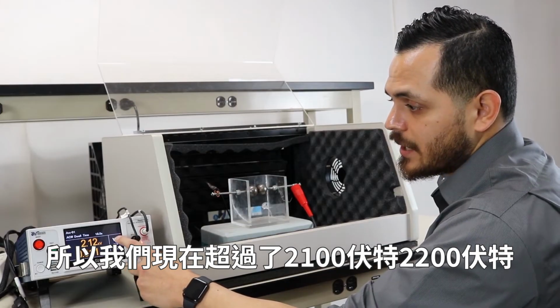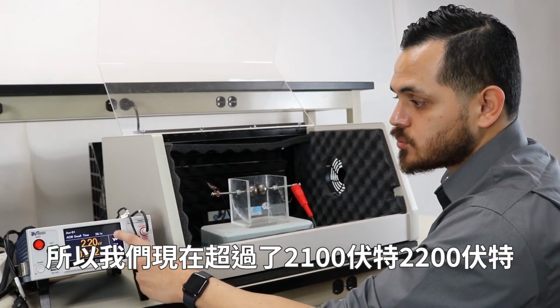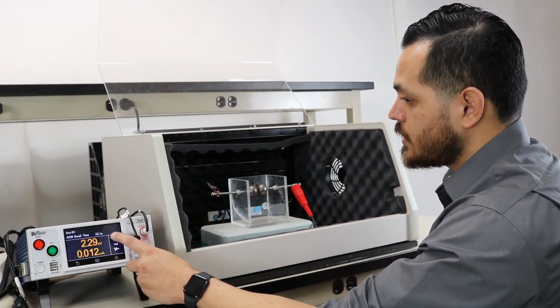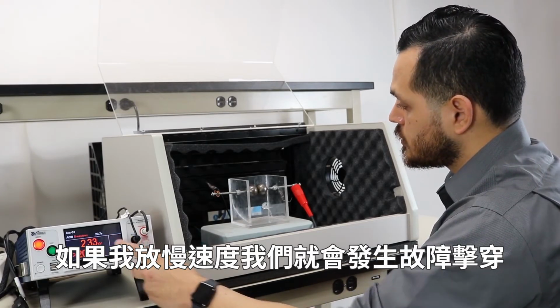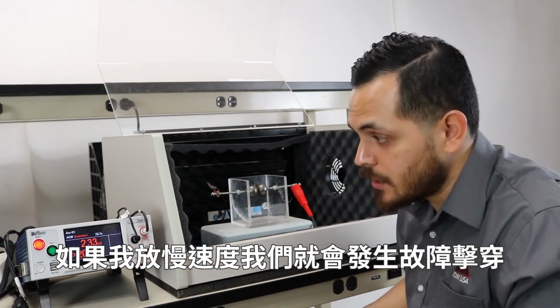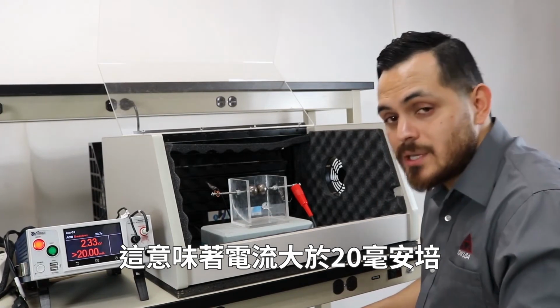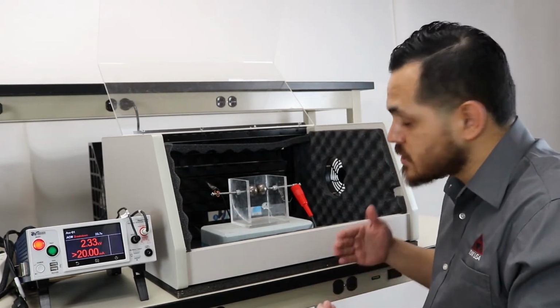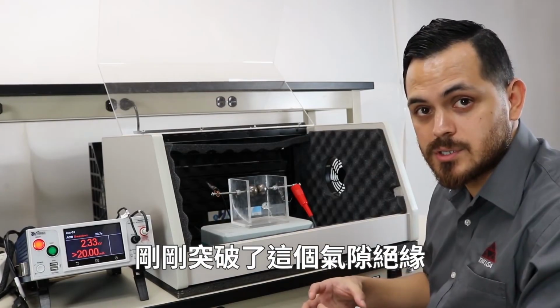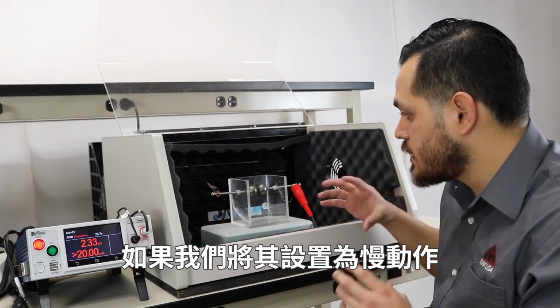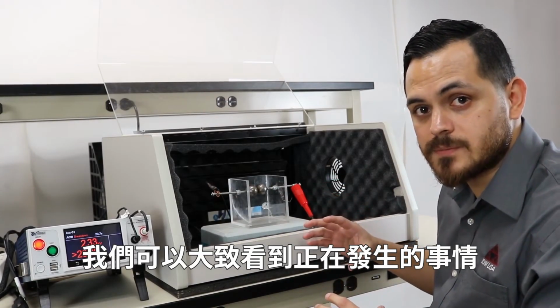So we're a little bit past 2100 volts, 2200. And if I slow down, we get a failure, a breakdown. That means greater than 20 milliamps of current just broke through that air gap insulation. And if we set it in slow-mo, we can kind of see what's happening.